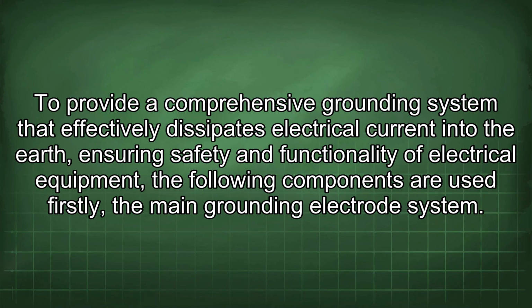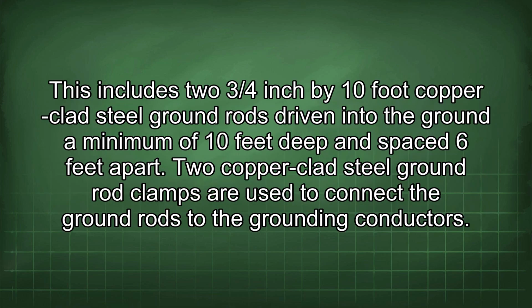provide a comprehensive grounding system that effectively dissipates electrical current into the earth, ensuring safety and functionality of electrical equipment. The following components are used. Firstly, the main grounding electrode system. This includes two 3/4-inch by 10-foot copper-clad steel ground rods driven into the ground a minimum of 10 feet deep and spaced 6 feet apart.